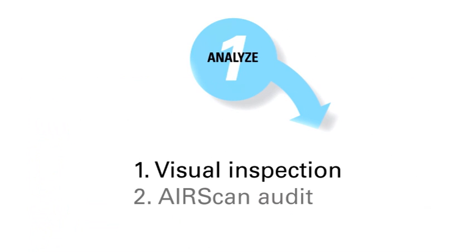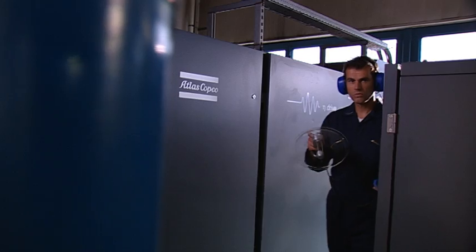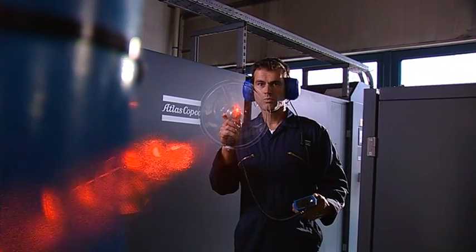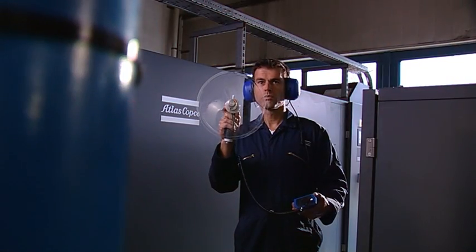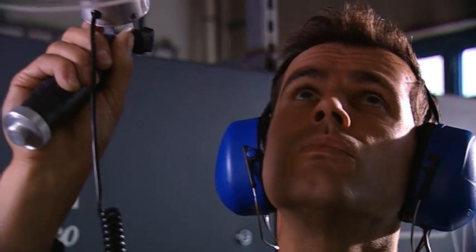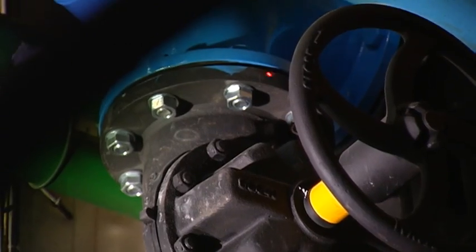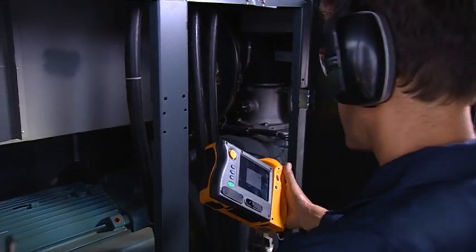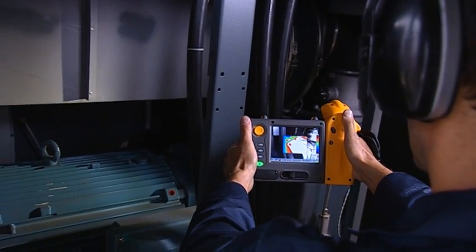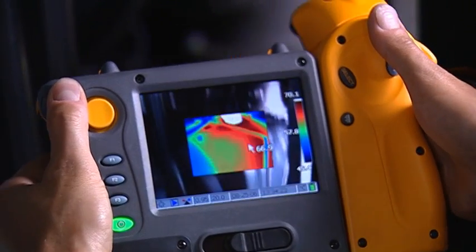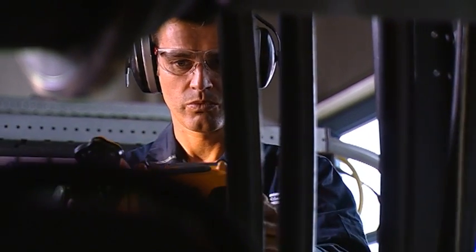The second sub-step is the AIRScan audit. While we want to avoid doing very detailed audits on installations with limited saving potential, we don't want to miss out on bigger saving opportunities by doing a limited audit. That's why we have a range of AIRScan audits tailored to the customer's needs, from limited checks for compressed air leakages to a full system audit and anything in between. System audits are based on actual measurements of the main parameters, such as power, current, airflow and pressure, and air quality, directly from the compressed air system.